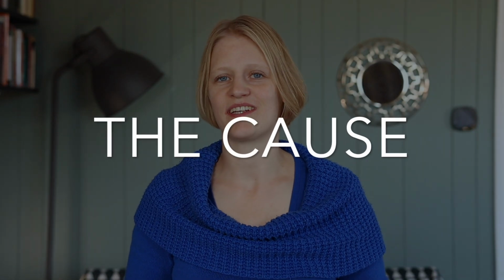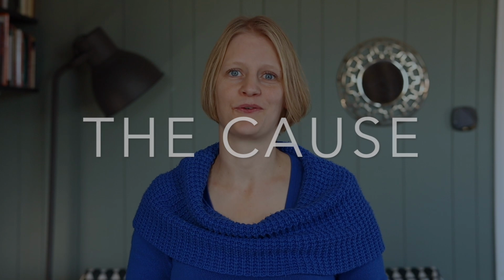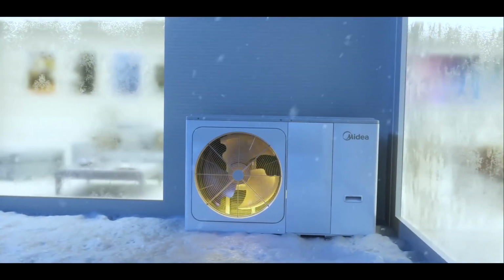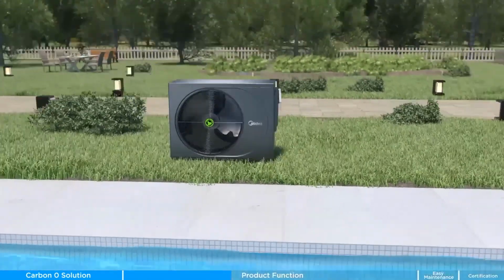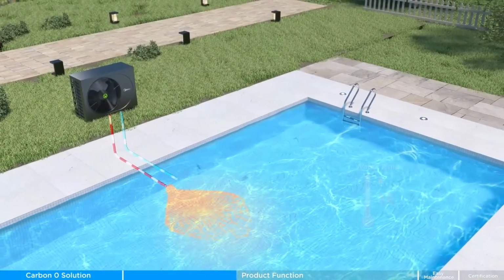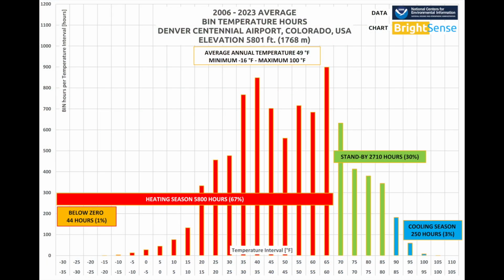Heat pumps are usually sized for a certain heating or cooling load at a certain extreme temperature. For instance, minus 15 degrees Fahrenheit, so about minus 26 degrees Celsius, or 105 degrees Fahrenheit, so 40 degrees Celsius, for example. But the climate looks like a bell curve, with only very few hours of those extreme temperatures. So in order to meet the load of those extreme temperatures, the units are vastly oversized the rest of the year.